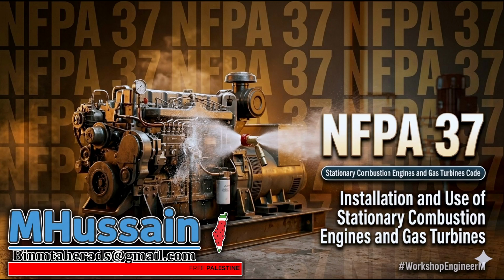For natural gas, you need a highly regulated gas train. The gas train, that's the sequence of valves and regulators, right? Yes, isolation valves, regulators, and crucial automatic safety shutoffs. If the engine stops, those valves slam shut instantly. But the source has made a really big deal out of propane versus natural gas. Propane is uniquely dangerous because of its vapor density. Natural gas is lighter than air. If it leaks, it floats up to the ceiling and vents out. But propane is heavier than air.